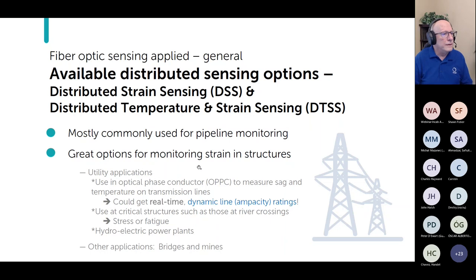And if you did that, you could sense the temperature, and from the temperature alone, you could get real-time dynamic line ratings. So you could know your actual ampacity in real time. And I think that's huge, because today utilities mostly rely upon static line ratings. And static line ratings are based upon some assumptions. And those typically are that the ambient temperature is 40 degrees C and the wind speed is 2 feet per second. So 2 feet per second is about 1.4 miles per hour, or for our international listeners, 2.2 kilometers per hour.